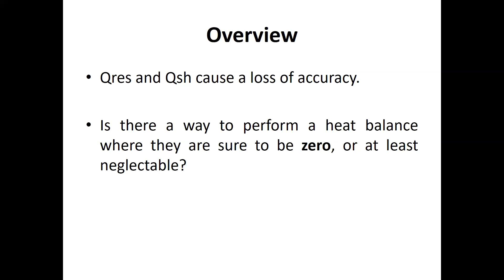So I wondered, is there a way to perform a heat balance where these quantities are sure to be zero, or at least to be negligible? The answer is yes. But for that, we have to find a period, or to perform a heat balance in a period before and after which the heating system is turned off, because that's the condition for having a zero Q residual and a zero Q shifted.